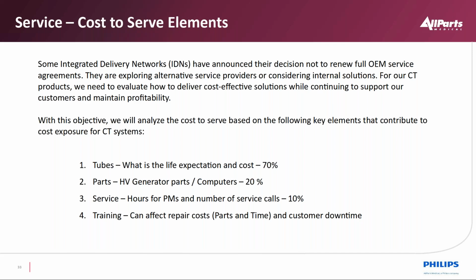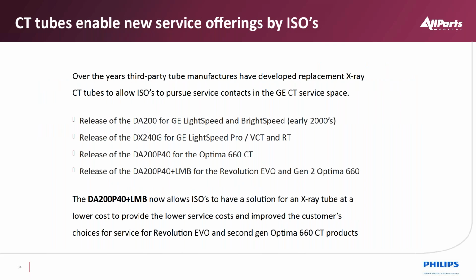Training can reduce your cost to serve because instead of replacing 2 or 3 parts, you would replace 1 in most cases. Sometimes you have to replace 2, but those parts are usually the lower cost in the end, like a transmitter and receiver that we have on the slip rings. Those 2 parts may be 10 grand completely, 5 each. So ordering both of those, sometimes when troubleshooting, is much easier than being down an extra day waiting on a misdiagnosis of a part. So training and parts are two of the aspects that reduce our cost to serve.